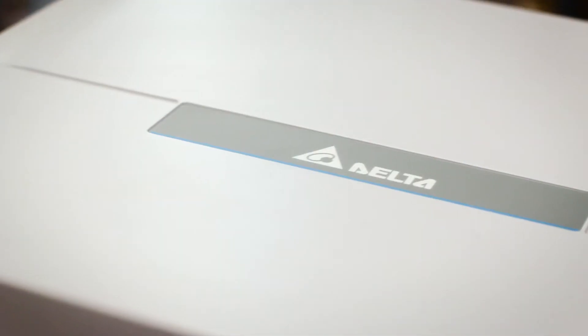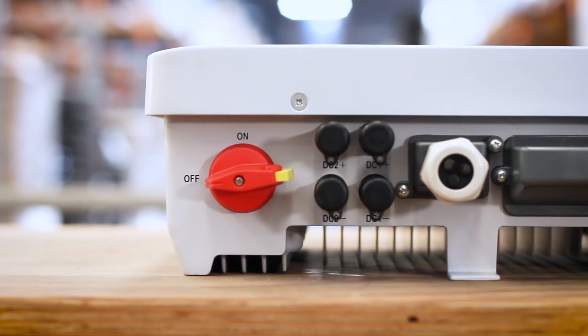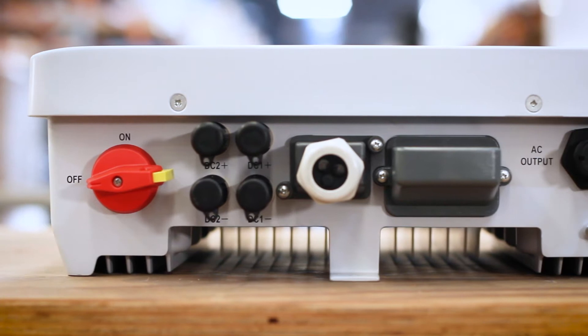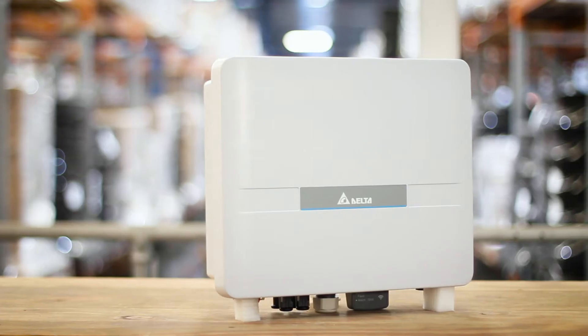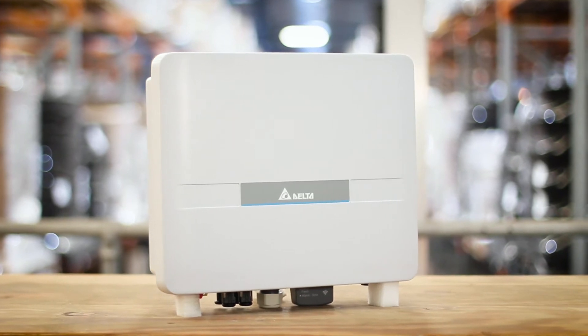The Delta H5A is a single phase string inverter with a built-in DC isolator. This series runs up to 20% longer throughout the day than any other inverter in its class, due to the ultra-low start-up voltage of 35 volts DC and a shut-down voltage of 30 volts DC, which allows start-up on just one panel, ensuring you get the most out of your panels from dawn till dusk.